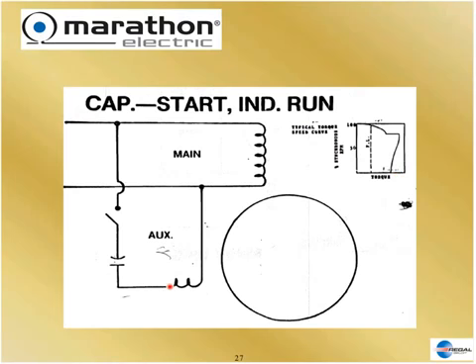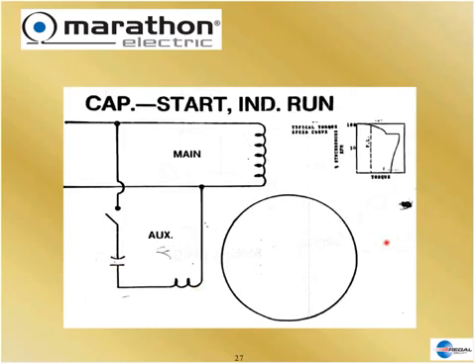We still have the switch, but we've added a capacitor. How did that capacitor produce all this extra torque? Electric motor coils have impedance that is frequency-sensitive and inductive. The capacitor has impedance also, but its impedance is opposite and inverse to inductive impedance. The capacitor negates the coil's impedance, gives us more pure power, and we get more starting torque.